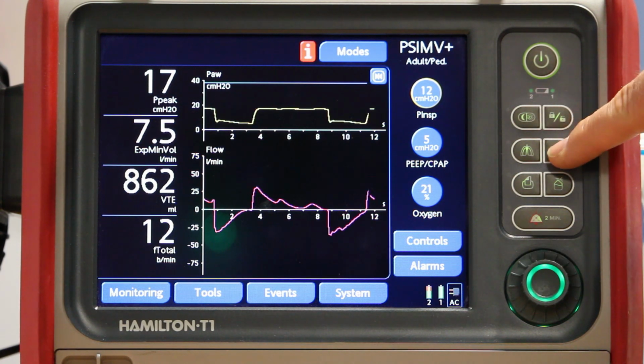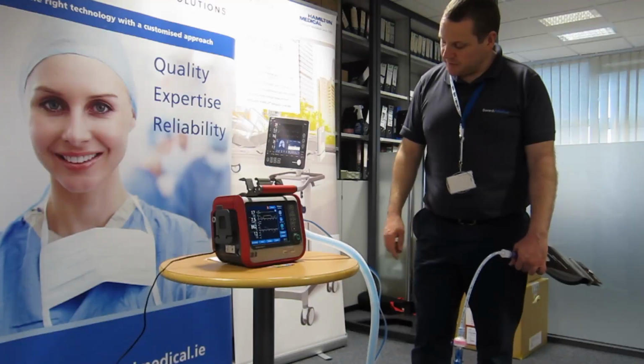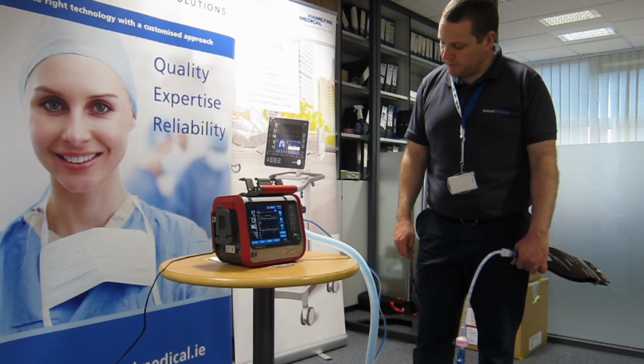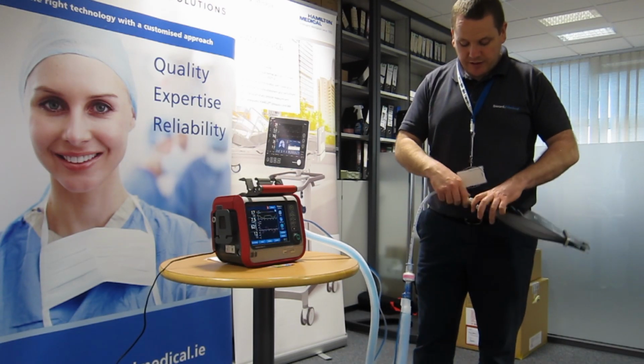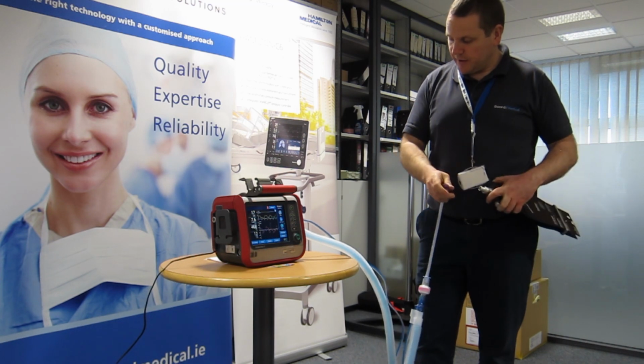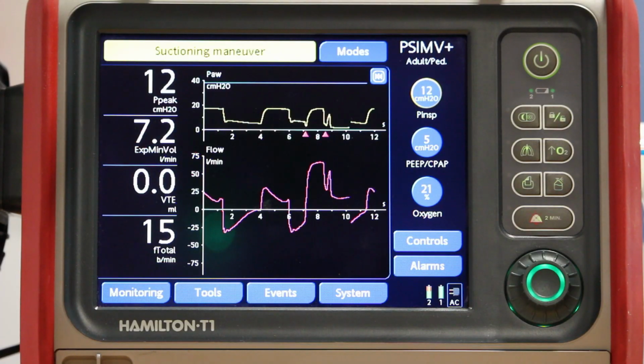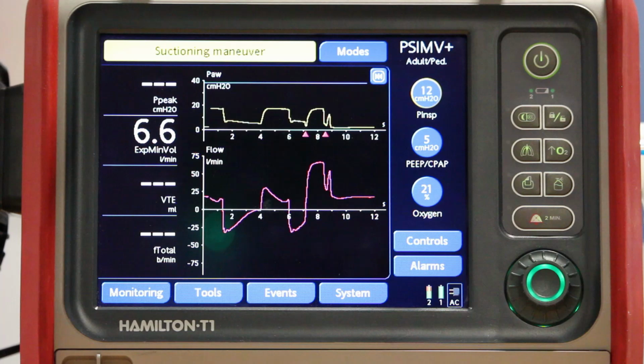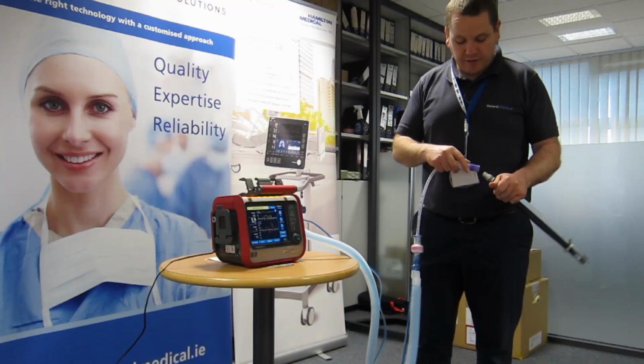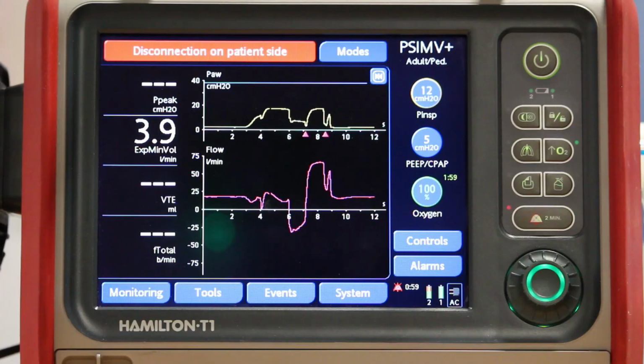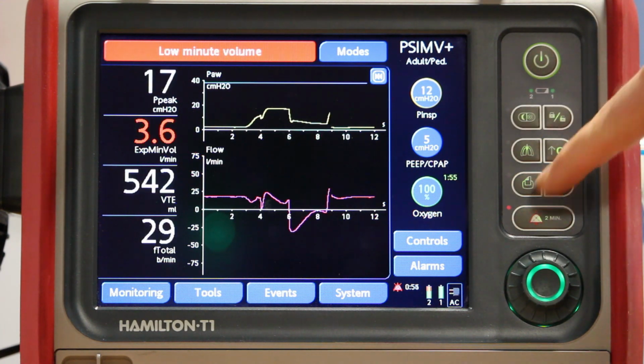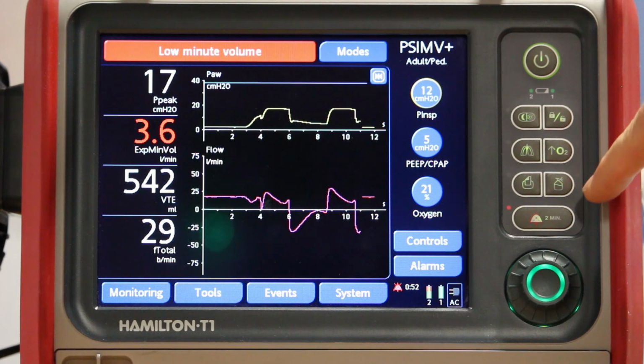I've got my O2 flush, so when I press it, it gives me 100% oxygen for 2 minutes, and then when I disconnect from the lung, it gives me a minute unalarmed to do what it assumes is a suctioning maneuver. When I reconnect, it'll automatically start to ventilate again, and it gives me 100% for 2 minutes for reoxygenation. So that's my O2 flush.